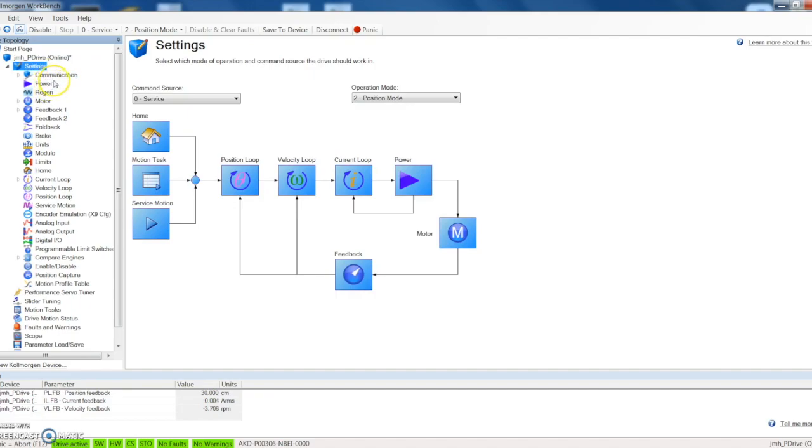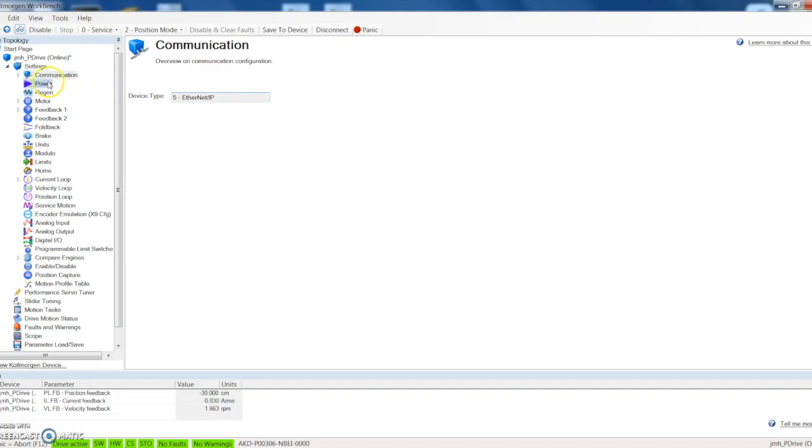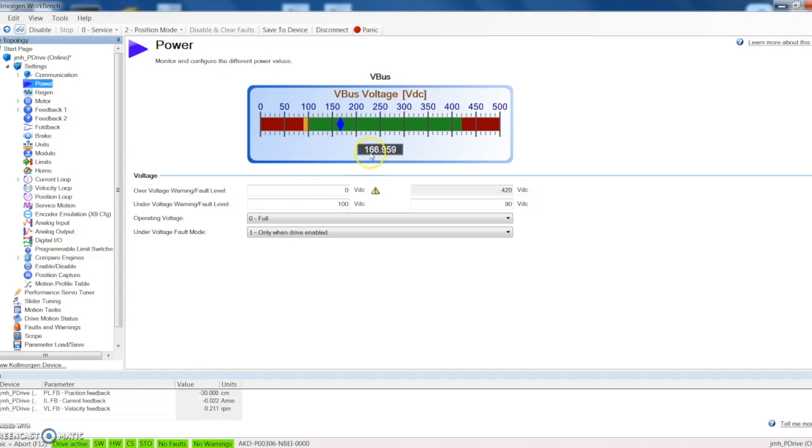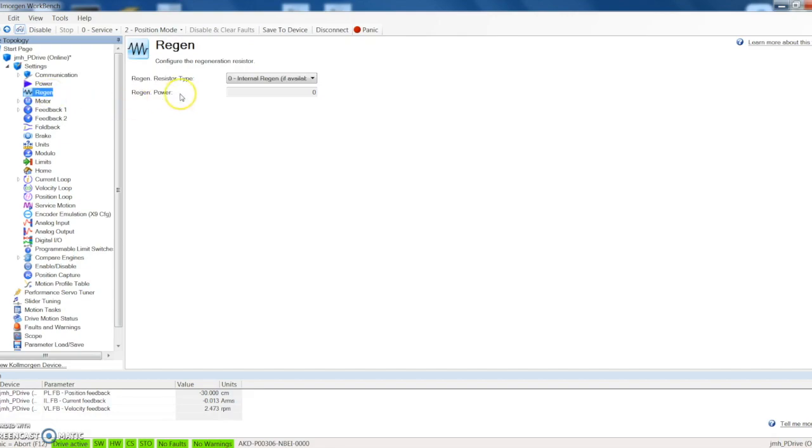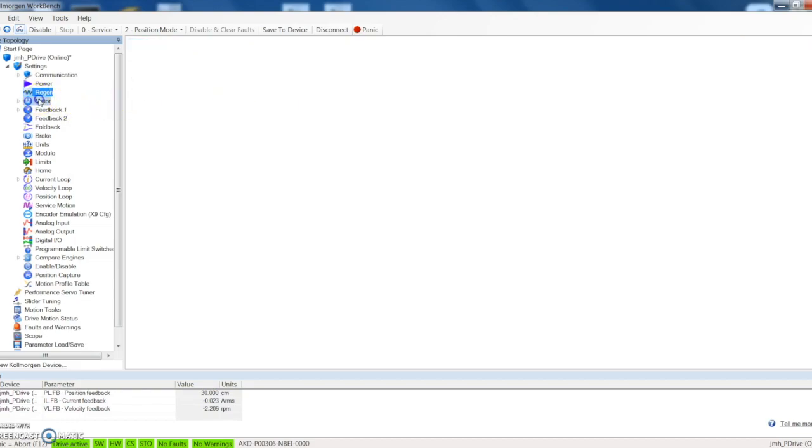You can go down here in some of the rest of the settings. Communication: that's just letting us know that right now we're using Ethernet IP. Power: this is just showing us what bus voltage we have, currently have 166 volts DC. Regen: we've got it selected to internal regen, any power that gets pushed back to the system can dissipate on the drive.